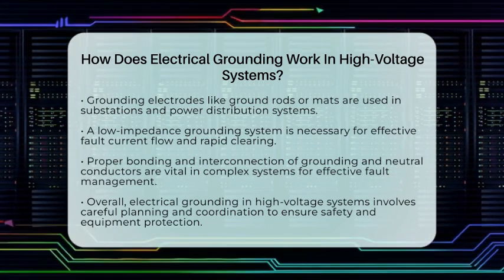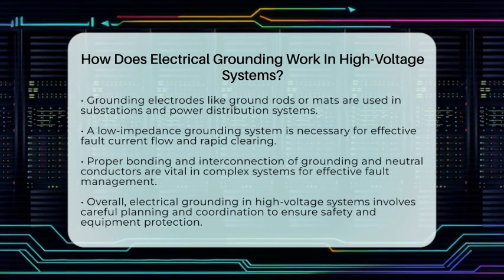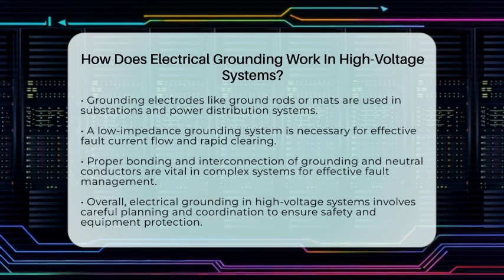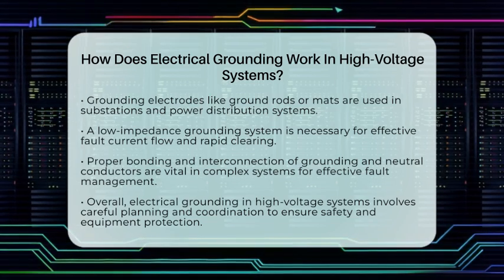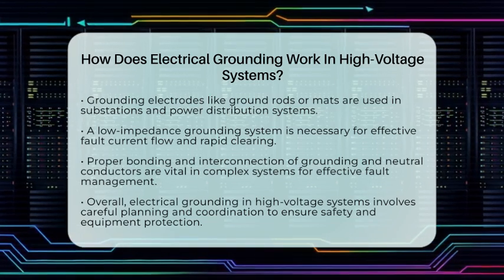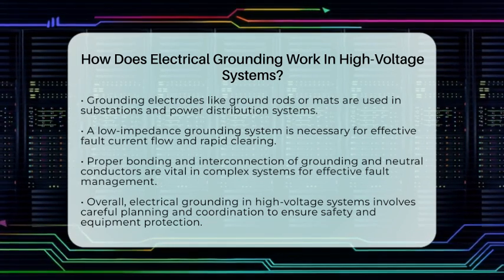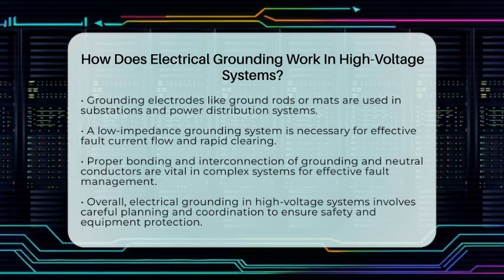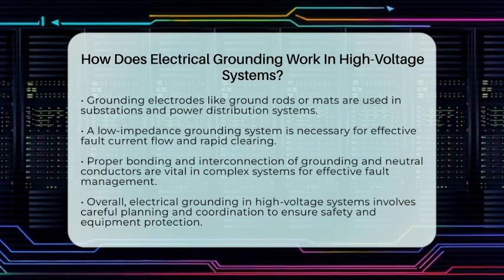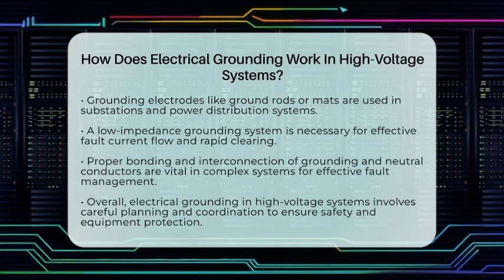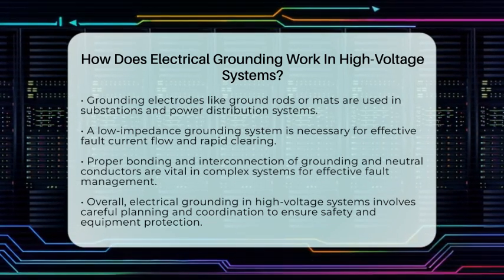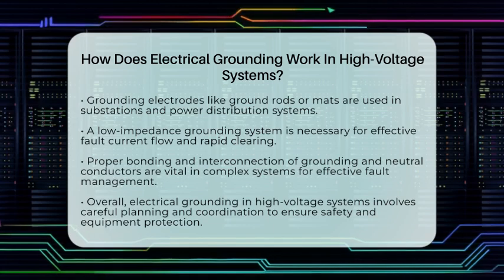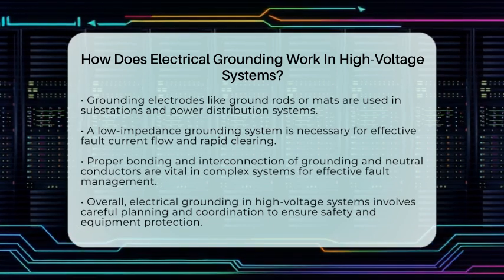The grounding system must have low impedance to ensure effective fault current flow and rapid fault clearing. In complex systems with multiple buildings, grounding and neutral conductors must be properly bonded and interconnected. This maintains a low-resistance return path for fault currents, ensuring that protective devices operate correctly.